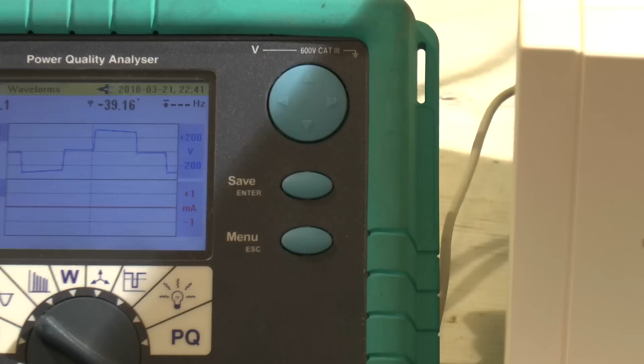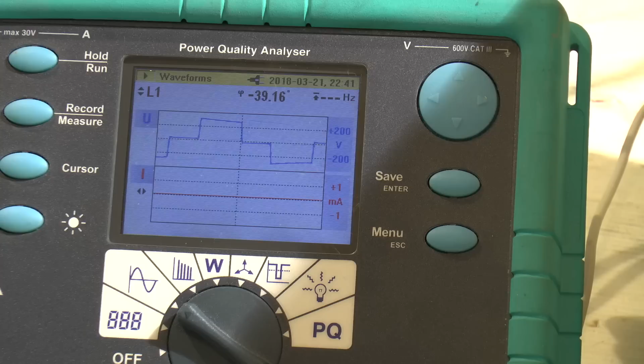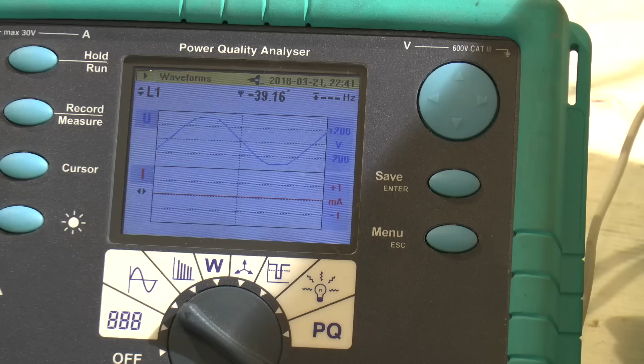It's fine for running switch mode power supplies because the first thing they're going to do is just rectify that output anyway. They'll rectify it, smooth it, and feed it into a chopper. But you wouldn't want to use it for feeding transformer loads or anything like that. Not least because it's only 800 VA and it's rated on the bottom at 540 watts. So that's another one checked out.